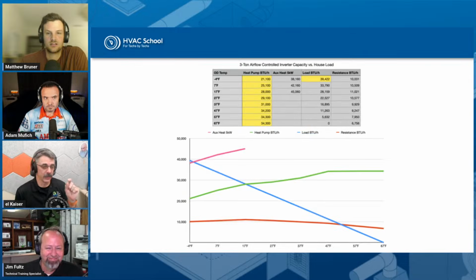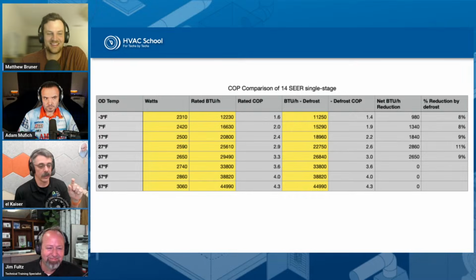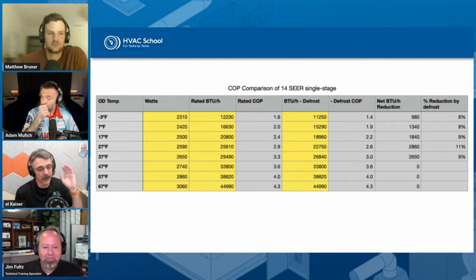To me, this chart right here negates a lot of the arguments that I hear about, oh, well, that doesn't include defrost, because yes, you can include defrost times in there. And the COPs are still above 1, even at -3 degrees Fahrenheit with a base. I mean, this is your most basic heat pump you can get on the market right now. So everything else above this is going to have better COPs.